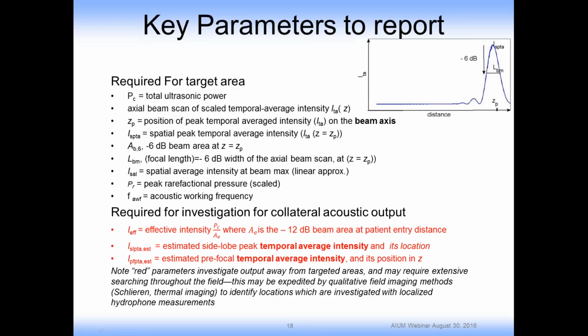A planar scan, a cross-sectional scan taken at this position, gives you the 6 dB beam area. Also shown here is basically the focal length, the 6 dB focal length of the axial scan at this position. We mentioned the ISAL, the rarefactional pressure peak, typically in these cases because of the linear approximation, it's at the same location as the ISPTA, and of course the acoustic working frequency.